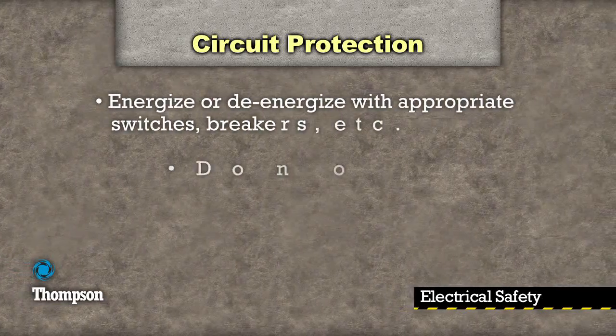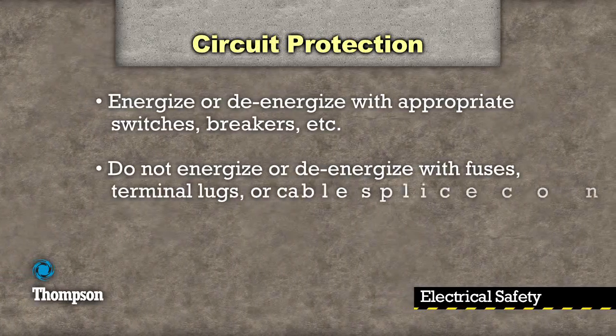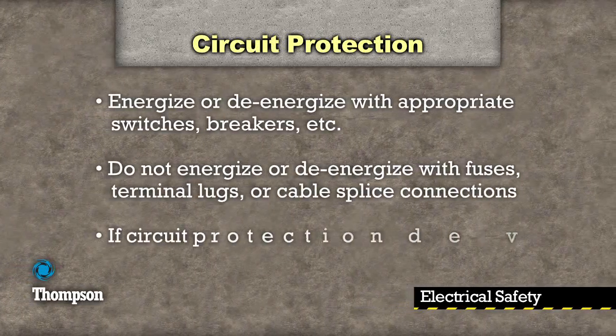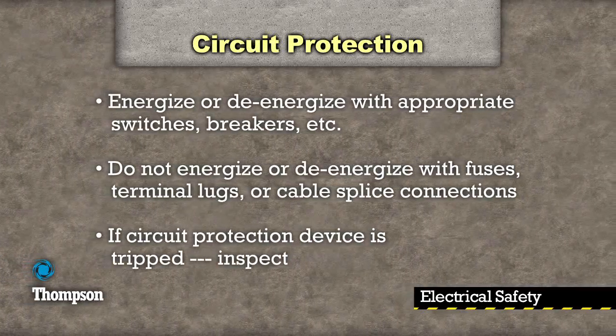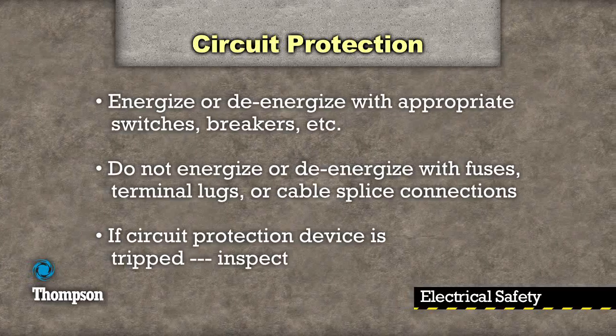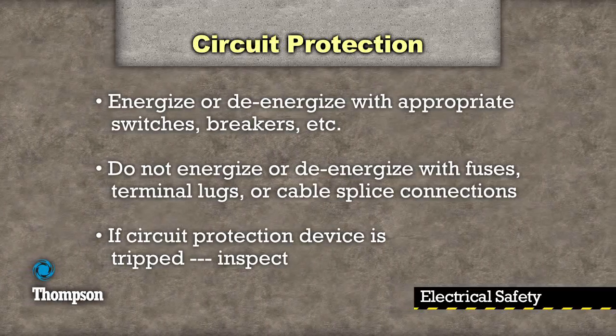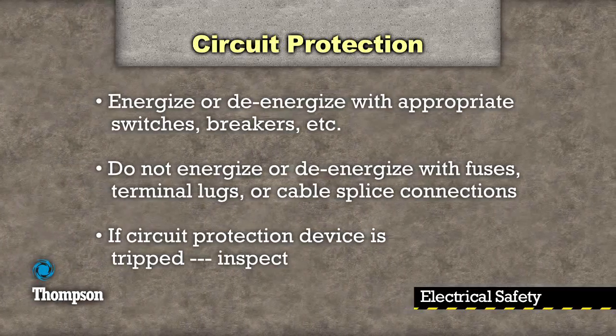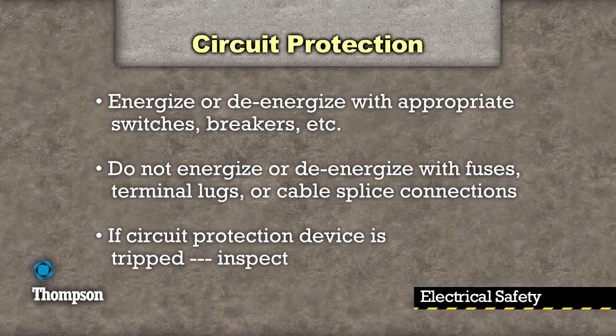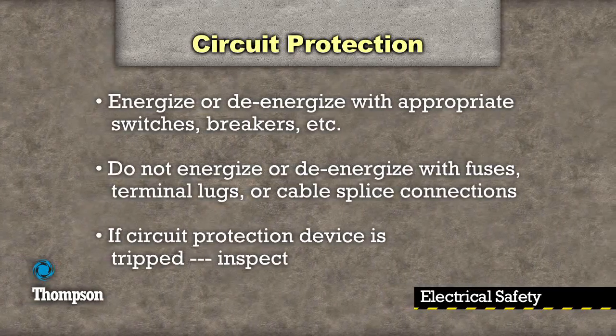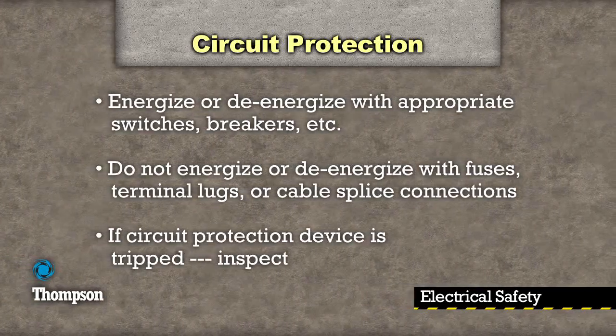Energize, close the circuit, or de-energize, open the circuit with the appropriate equipment such as switches or breakers. Do not open or close circuits by installing and removing fuses, taking terminal lugs on and off, or by splicing cables. If a circuit protection device is tripped, have an authorized worker inspect the system before manually re-energizing the circuit. There may be a short or some other electrical hazard that needs to be repaired.